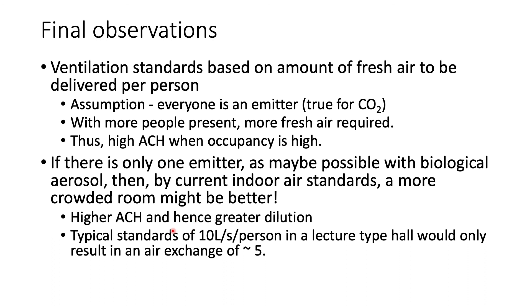That's something that I think needs to be reconsidered in the context of the pandemic. The typical standards that we are calling for, 10 liters per second per person, would result in a lecture hall having an air exchange rate of about 5, which we said would be inadequate when you consider particles in the size range of 500 nanometers to 5 micron, which could carry pathogens such as SARS-CoV-2. We really do need to re-look at the standards from the pandemic perspective. That's all I have for today. I appreciate everyone's patience. I look forward to your questions. Thank you.